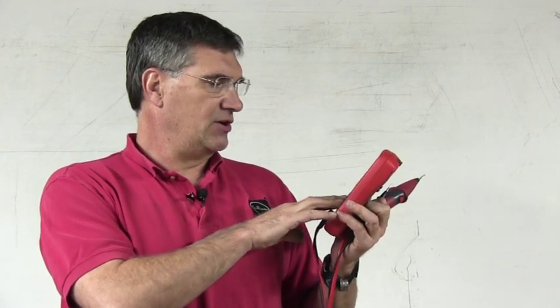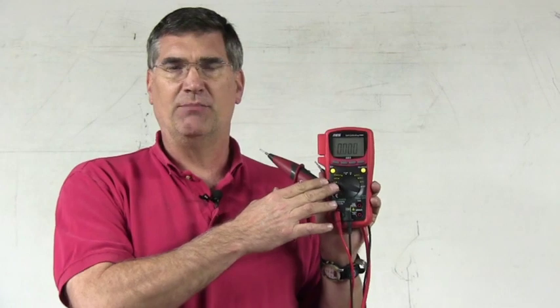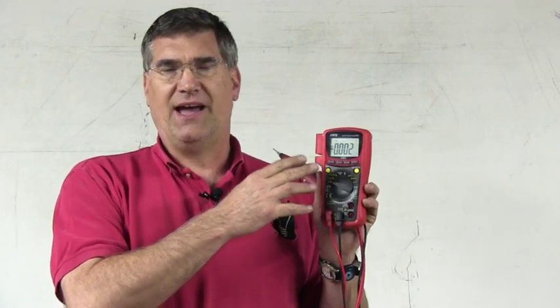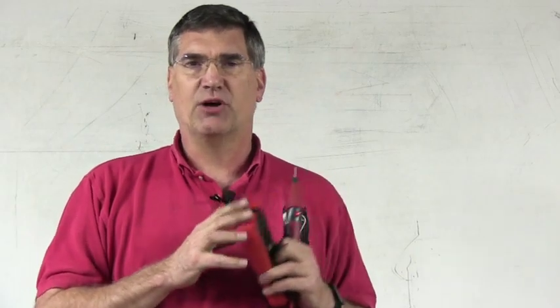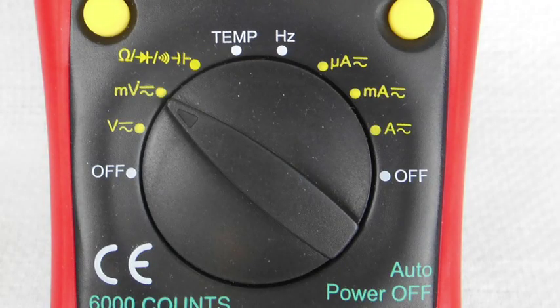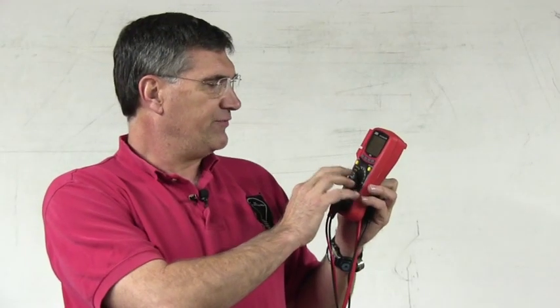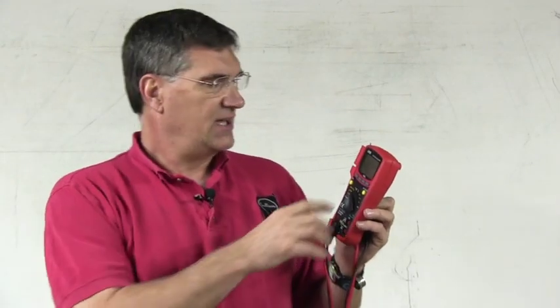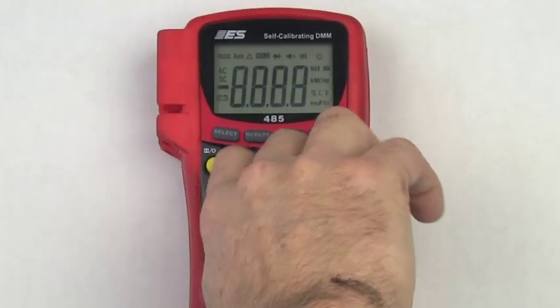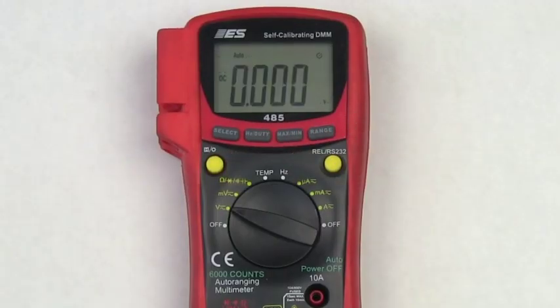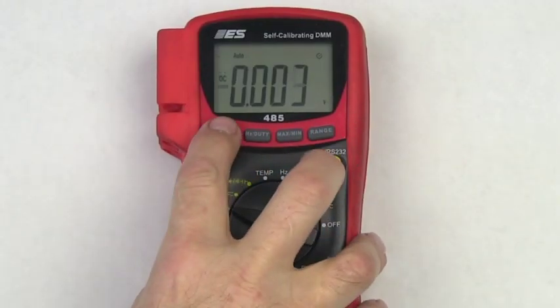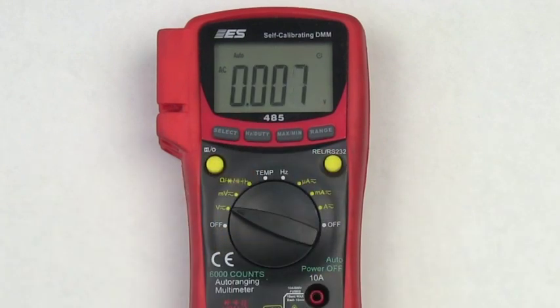Another consideration is that you have a separate millivolt scale. So at times when you're trying to measure the voltage drops across fuses or make other small measurements, you might have to actually flip from the voltage to the millivolt setting. The meter defaults to DC volts, and if you want to flip to AC, then you simply press the select button, which moves you from DC to AC and back. This is true for the voltage and the millivolt settings.